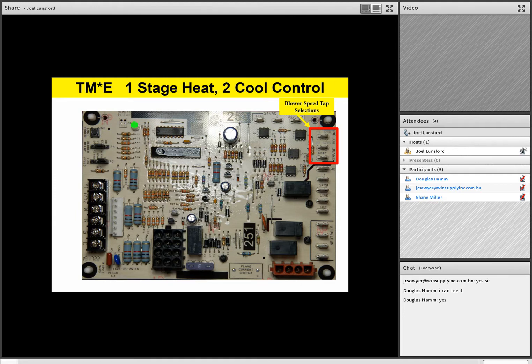Okay, team, if we move down the board, we see we have an EAC terminal. That EAC terminal is a 120-volt AC output for an electronic air cleaner. L1 is where we power up the line voltage components on this board. This is where the 120-volt AC comes into the board to power up components like the hot surface igniter and the transformer and so on. So this is the L1 or high voltage input to the board.